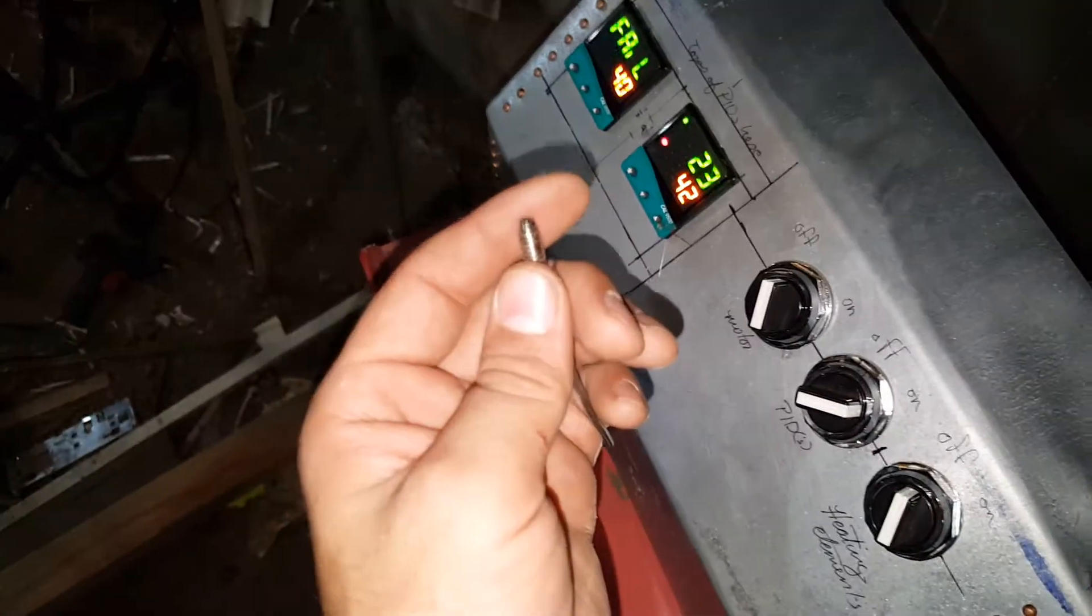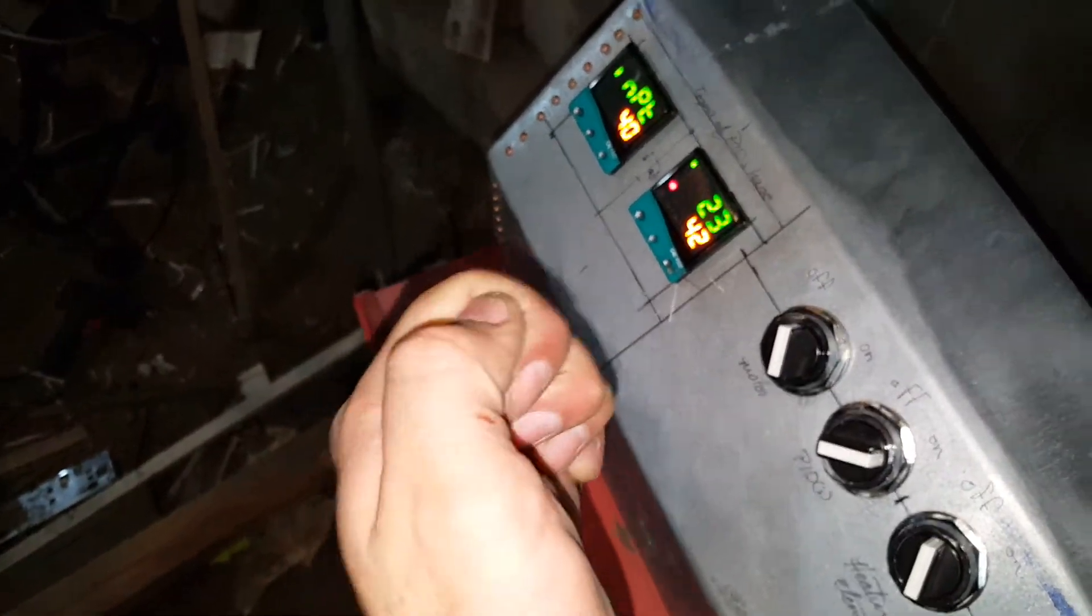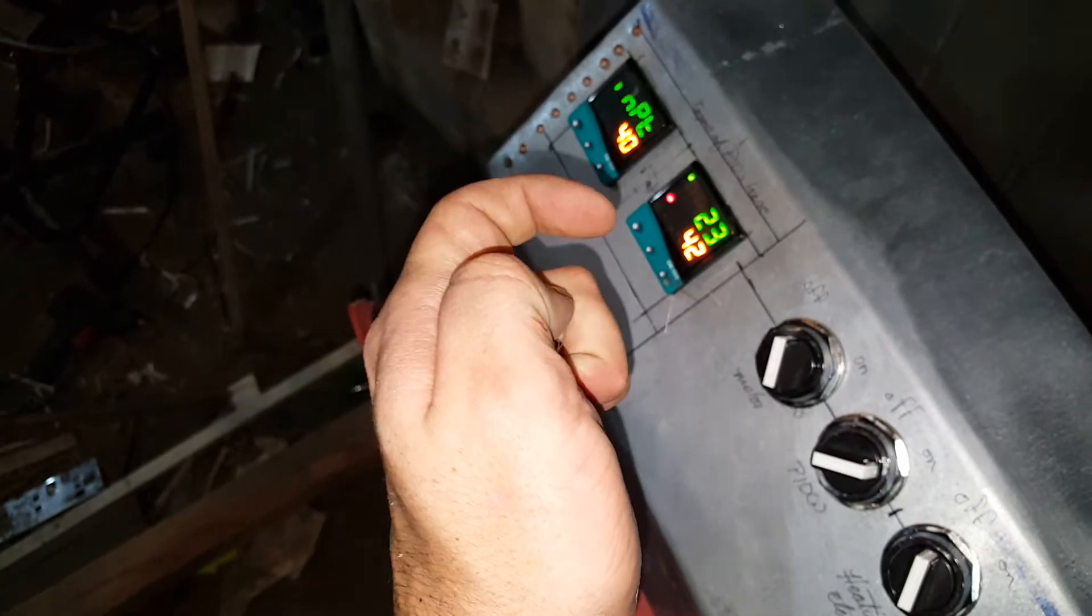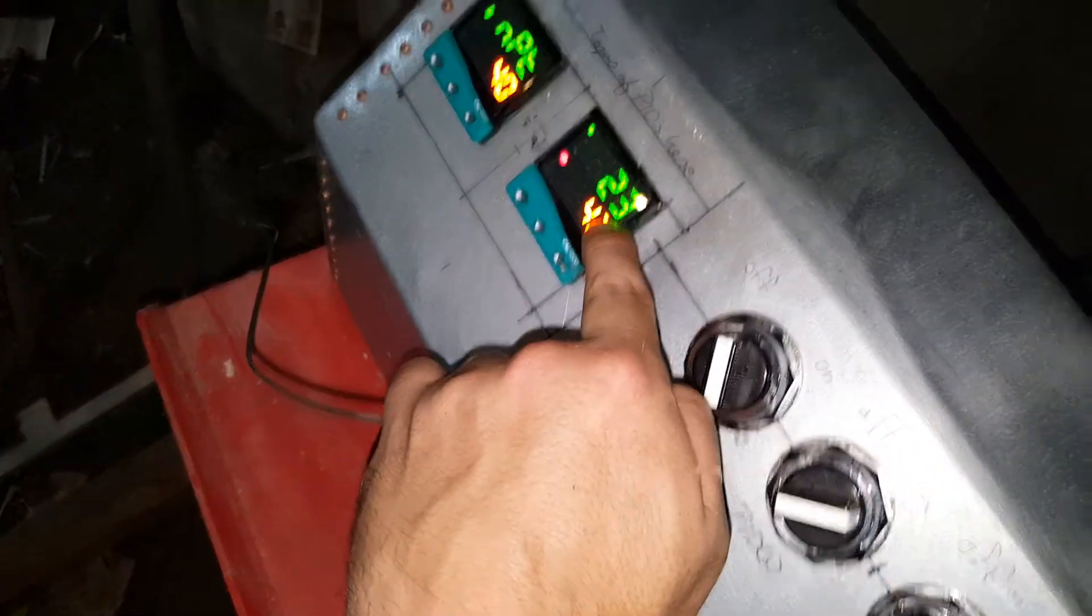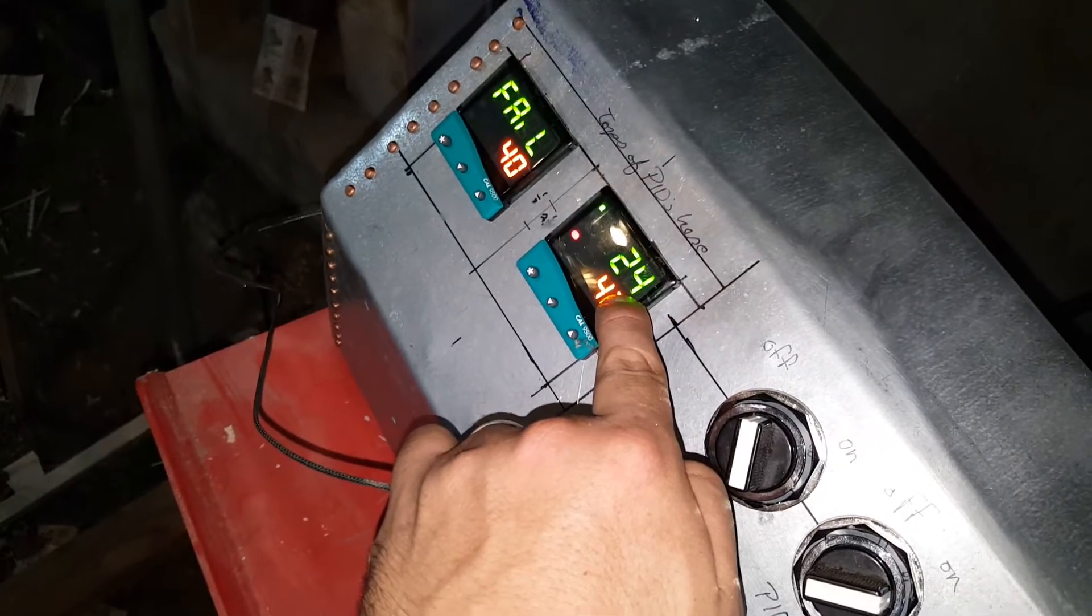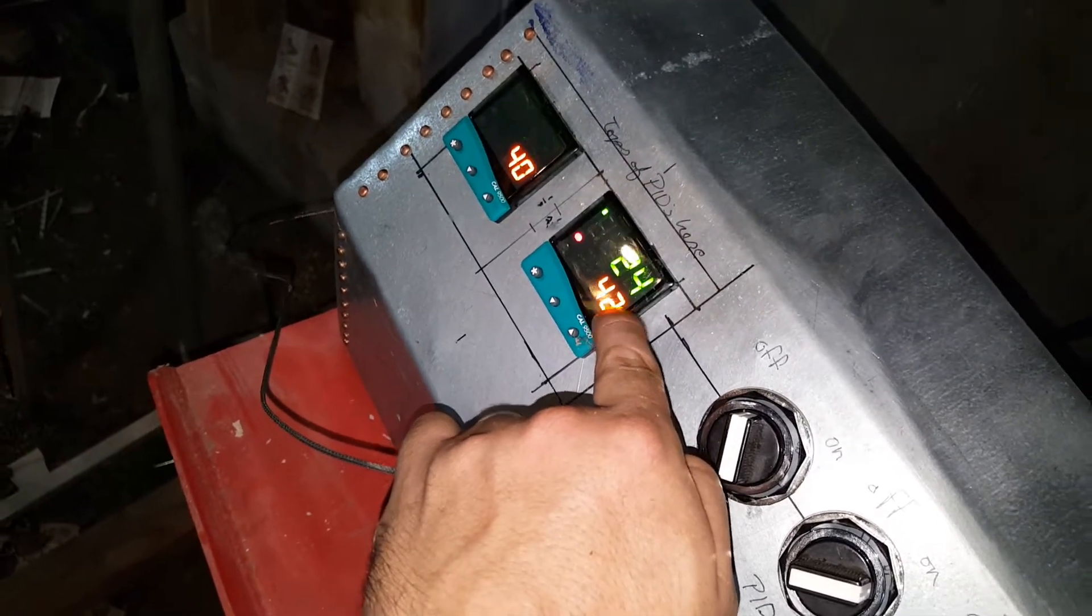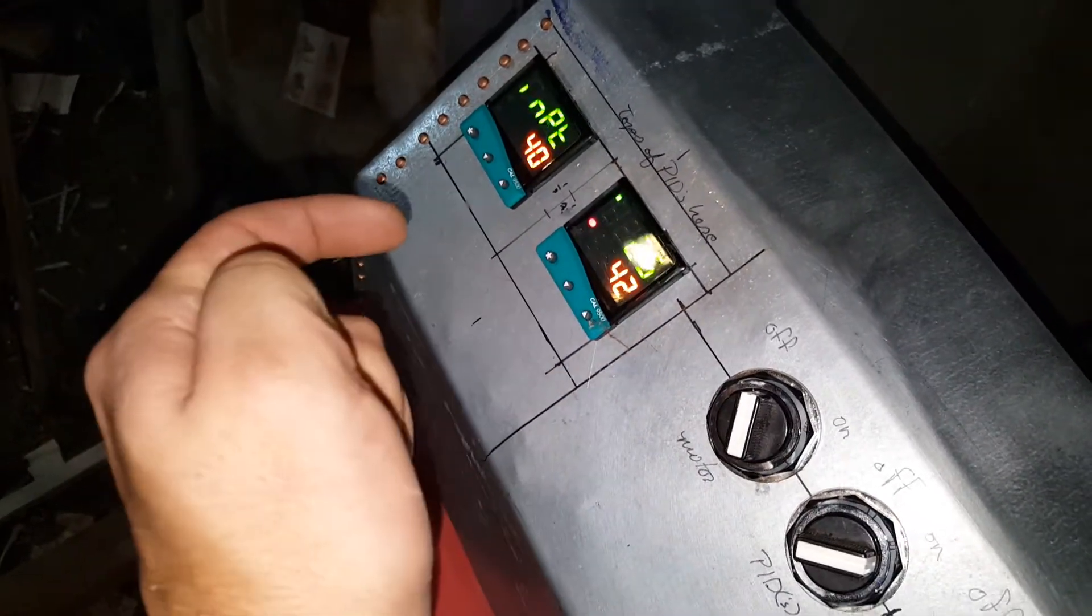Input fail. That means that the thermocouple is not installed. If I hold down on the thermocouple, the temperature on the one on the right here should go up. There we go, as it starts to get to my body temperature.